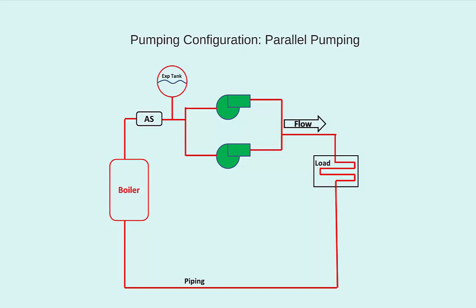Often, the control sequence would be to operate one pump for, say, 100 hours, and then the next pump for 100 hours, equally distributing the wear and tear on the pumps. If you are going to do this type of schedule, however, it is best to stagger the total operating hours between the pumps by a few thousand hours. Otherwise, you might have both pumps crap out on you at the exact same time, which would completely negate this idea of full redundancy.